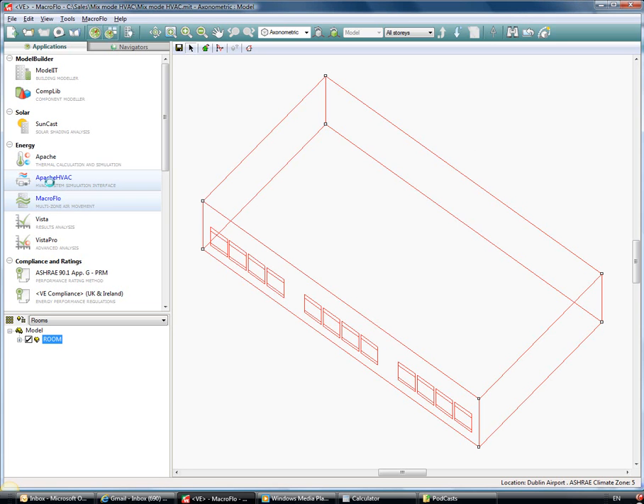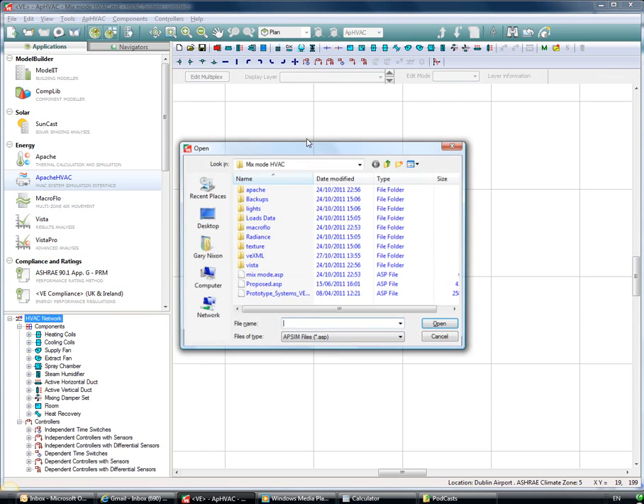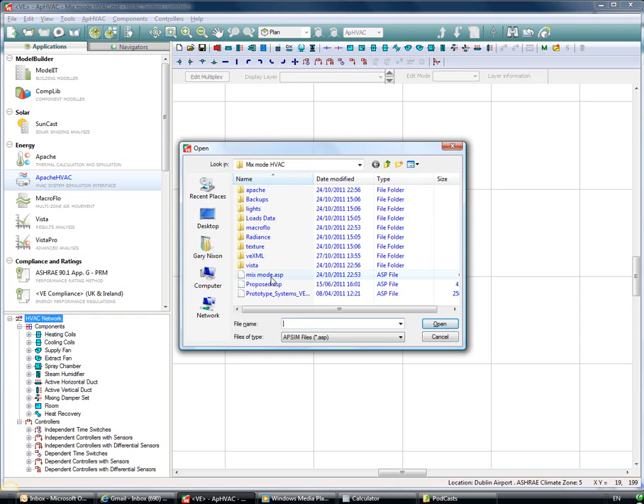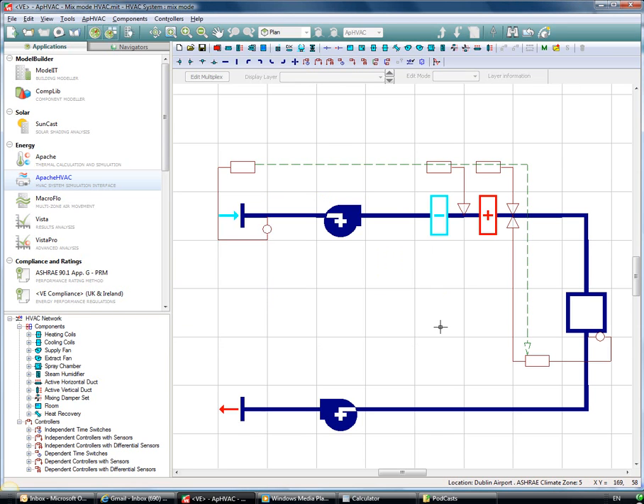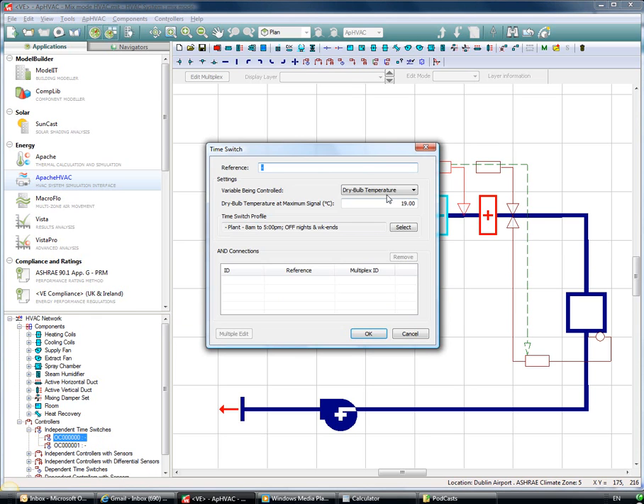As I then go into Apache HVAC, I can see what's put in here in terms of the system. And I can look at my mixed mode ASP file, that's the file associated with Apache HVAC. And I can see when I open this it has a small network, quite a simple network, just to show us what's happening. In this case, though, we have our cooling and heating coil which is conditioning the air up to 19 degrees C. It is coming on between 8 and 5 in the day and it's off on the weekends, so we only have air flow and heating between that time.